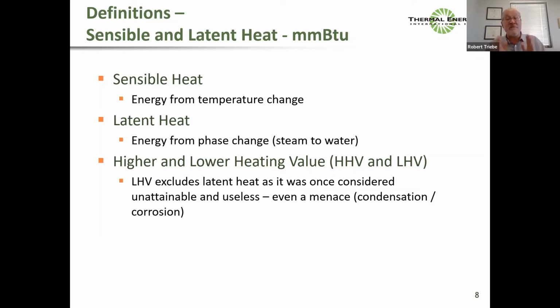It was even considered a menace, in that if you got cold enough in your exhaust gas to get the latent heat, that meant you were condensing. If you were condensing, you were ruining your boiler or you were ruining your stack, because of the condensation and corrosion. And so in fact, you wanted to avoid using that latent heat because you didn't have systems that were designed and capable of taking advantage of it.